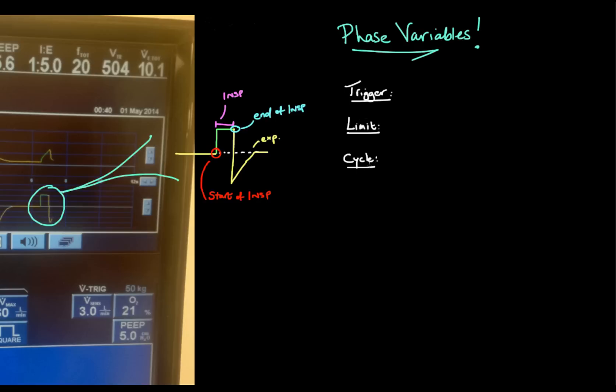These might look pretty foreign at this point but we're going to talk about what they are. A trigger variable is what causes the start of inspiration — what triggers us into inspiration, what causes the ventilator to go from expiration to inspiration. Whatever causes the start of inspiration will be our trigger variable — what is it that's telling the ventilator to go from expiration into inspiration.